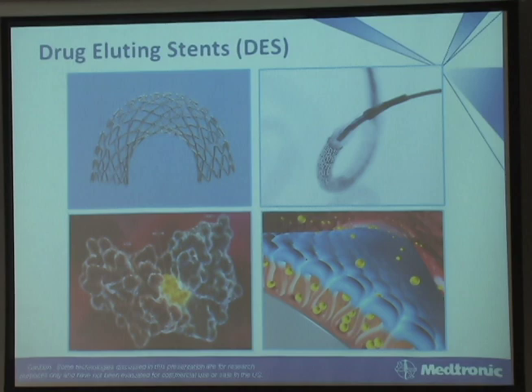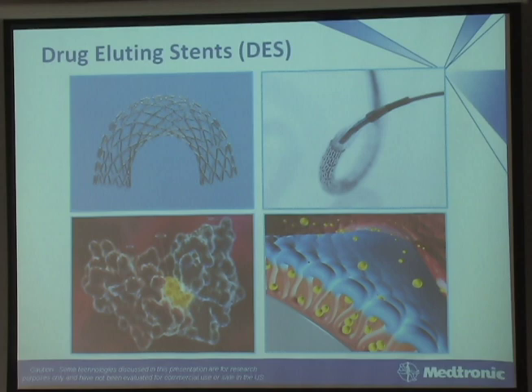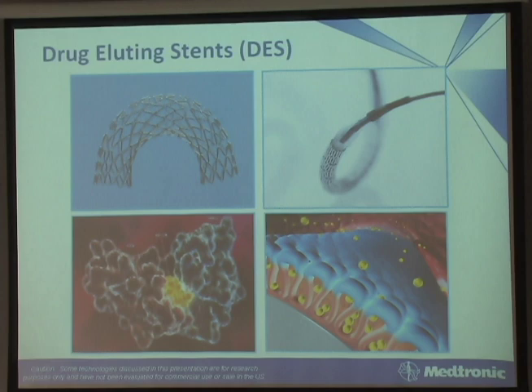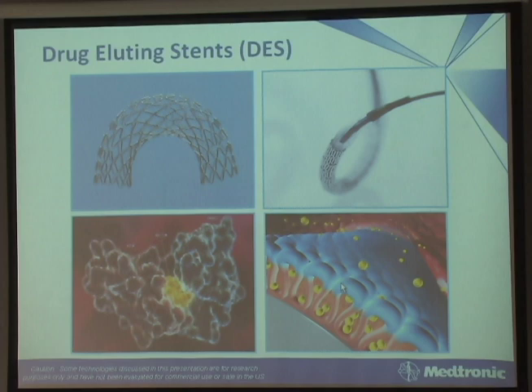The second big factor is the push for combination devices. When you open up the blood vessel, you end up doing some damage to the wall and creating scar tissue formation. What has now become standard of care is drug eluting stents. People took pharmaceuticals being used for oncology and said, hey, these are really good at stopping tumors from growing — can we put these onto a stent and use that to influence the wound healing, scar forming response? A drug eluting stent basically has four different portions: your delivery system or catheter, your stent, your API or pharmaceutical that prevents restenosis from forming — the anti-proliferative — and you also need a coating because if you just put the drug directly onto the stent, it will come off right away. The rate at which you deliver the drug to the tissue is very important, and in order to do that, you need to have a good coating.